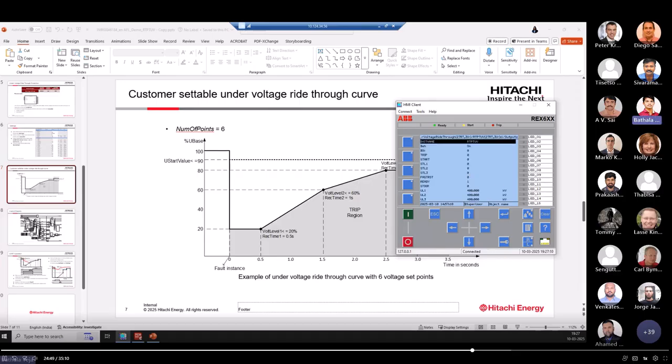Here again, I will apply under voltage condition. Immediately I will recover the voltage from 85% to 100%. You can see here I applied 85%. Immediately I applied rated voltage, but I think it missed applying within 2 seconds. That is the problem with such a short period of time.